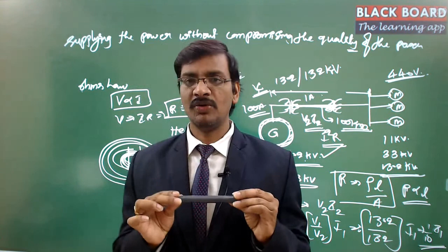Another important factor we have achieved is reducing I-square-R loss. I-square-R loss is nothing but the power consumed, which is used in generating heat throughout the line. If you notice, power P is directly proportional to I-square. R is anyway decided, because once the line is designed, it will possess a certain value of resistance. Hence I is the one which decides the amount of power. If you reduce that I value, its square is reduced even more.